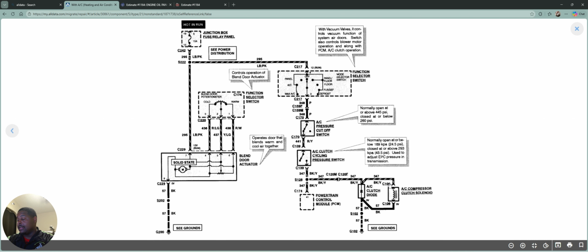If you do not get a reading close to 0 or less than half an ohm, 0.5 ohm or less, roughly, if it's 0.6 ohms, 0.7 ohms, it's all right. 0.5 or lower is best.